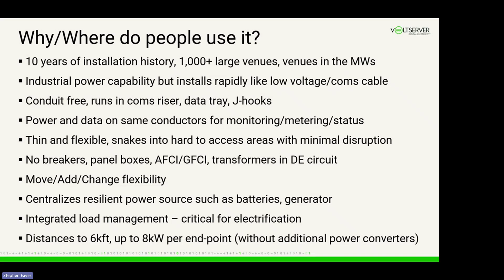Capabilities are about 6,000 feet distance from transmitter to receiver, and about 8 kilowatts of power at the endpoint. So this isn't for giant electric motors, like 100 kilowatt motors—it's for smaller point-to-point distribution. But with power electronics, we can parallel units and get to very high power levels.